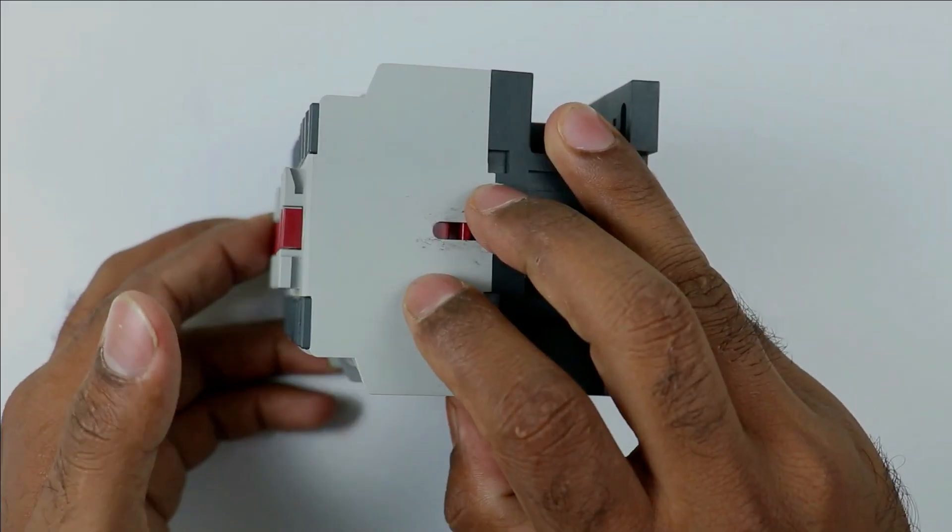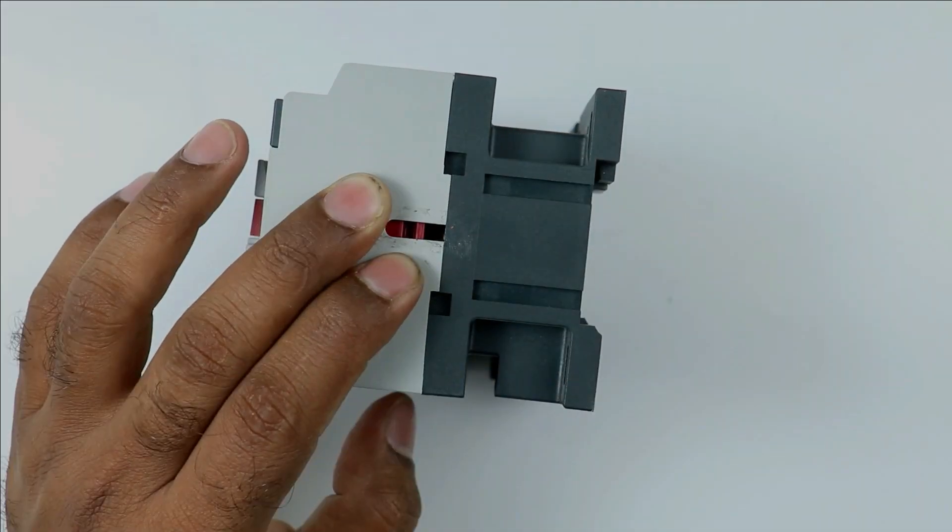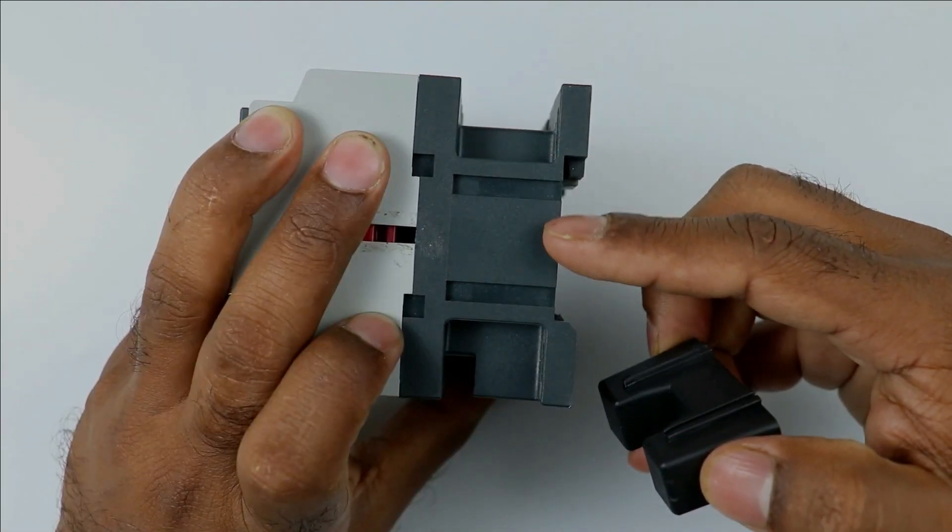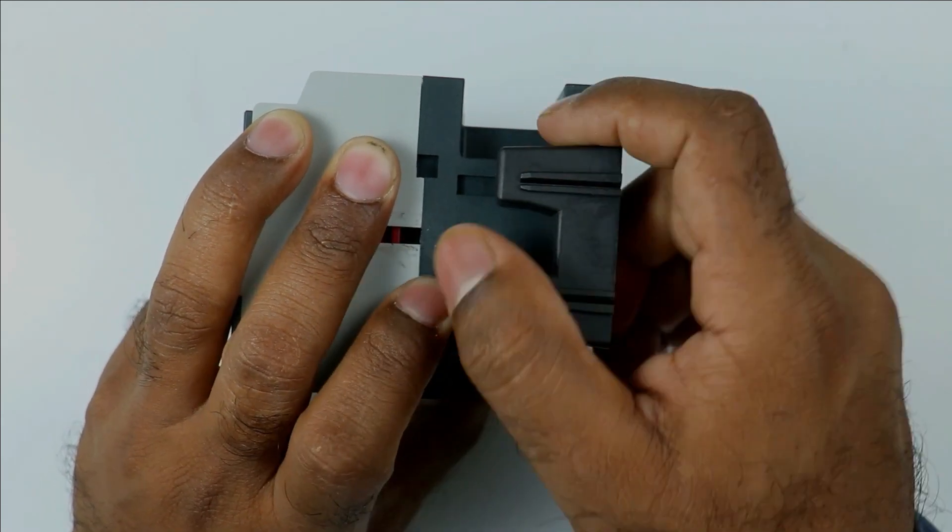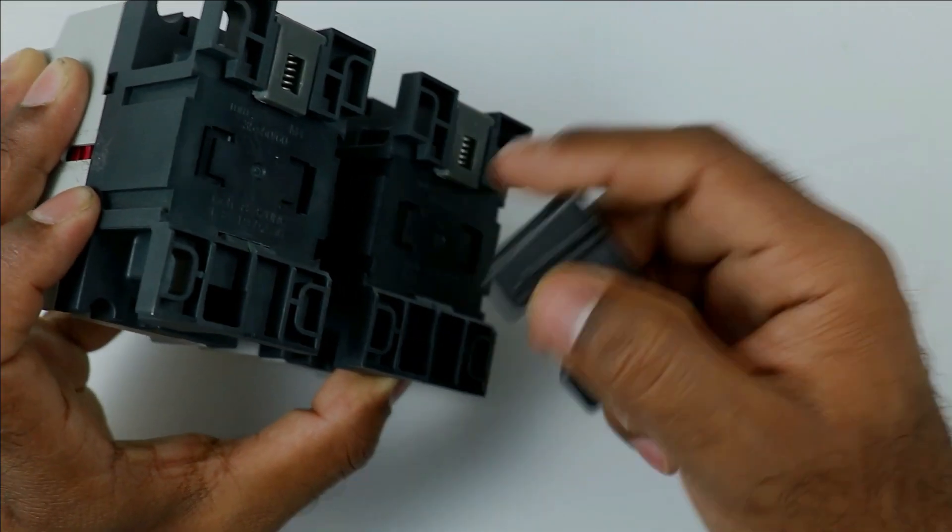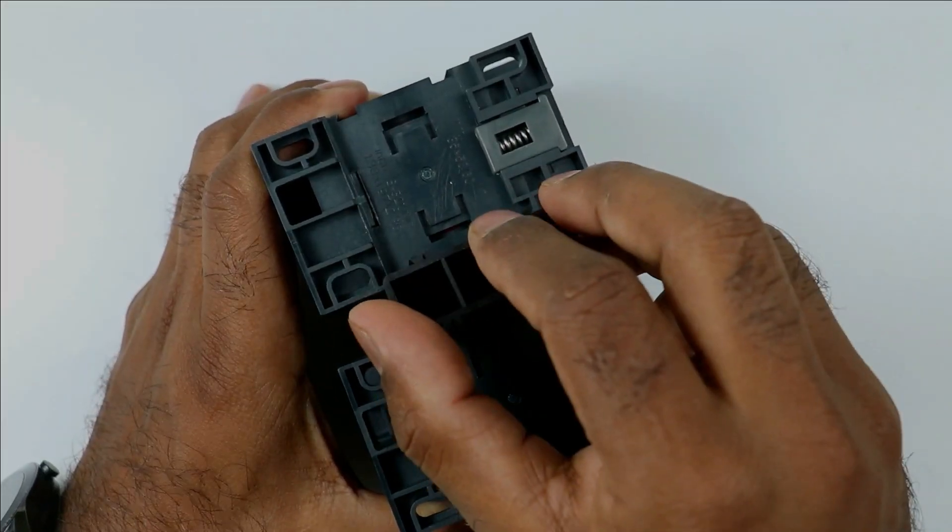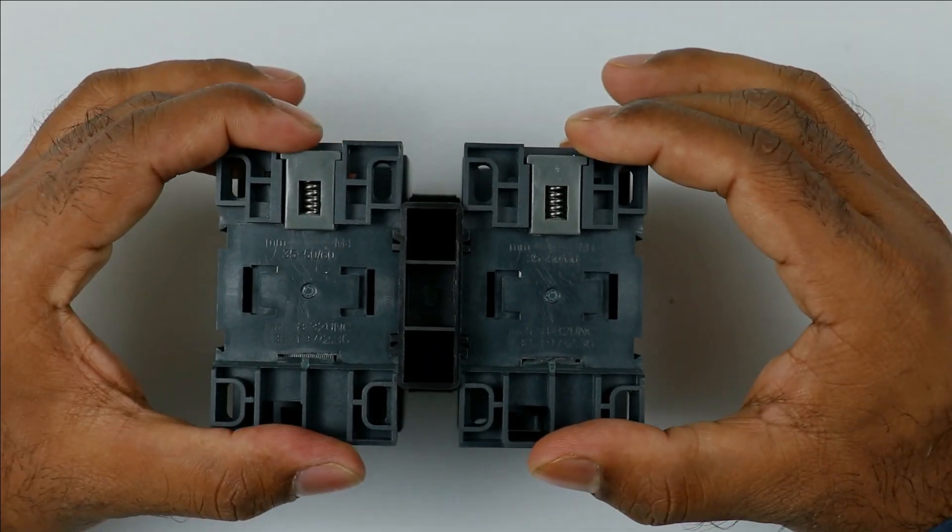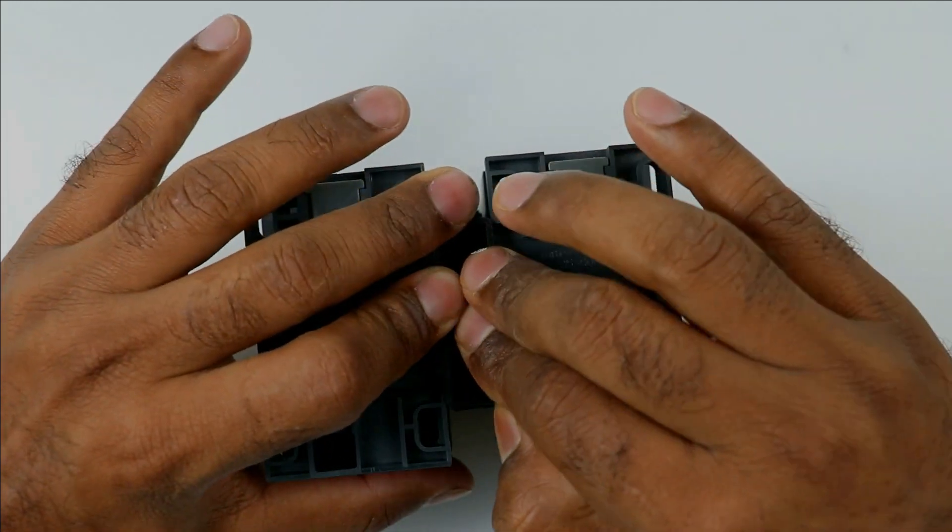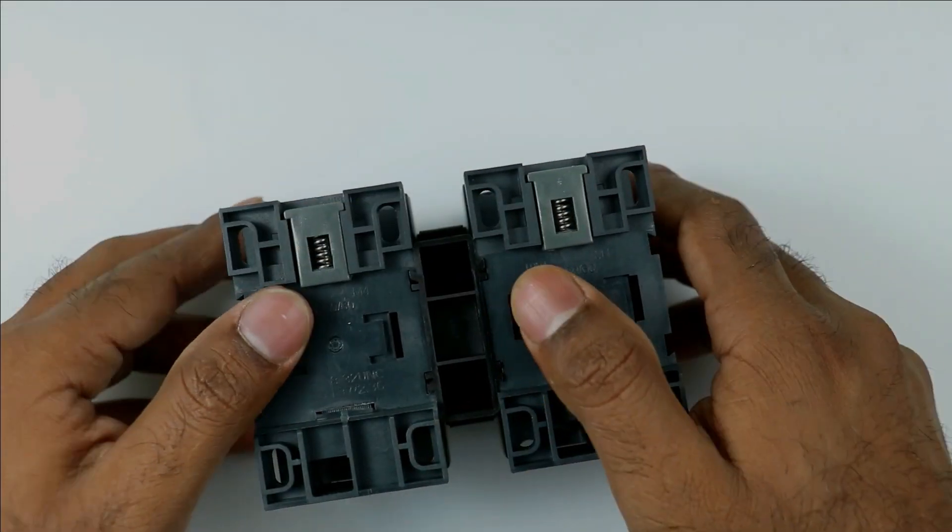I am now keeping the contactors like this. When placed like this, put this cover in middle. Still this portion here, in this way mount here. Don't mount on upper side, mount in this side only, where the mechanical interlocking was done. So I mounted this here. If I even try to pull these, it won't come out. Press this cover even more. Now our contactors are interlocked mechanically.